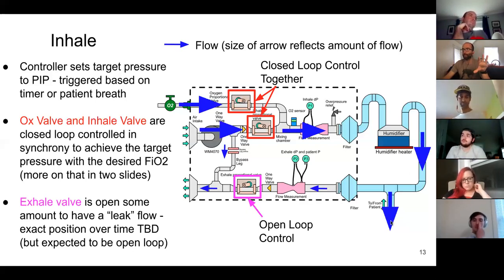We still haven't measured pressure, right? Just explaining that. The pressure that's generated here that's not being measured is going to the patient. And then that pressure also propagates through this piping into the flow measurement section. That's where we pick up pressure. So there's an issue there in that there's a difference in the pressure that's generated here and where it's controlled here. There's both a physical and time lag. The time lag is really small, but the physical lag is actually somewhat significant in the sense that there's pressure loss on this piping. But that's what goes to the patient.